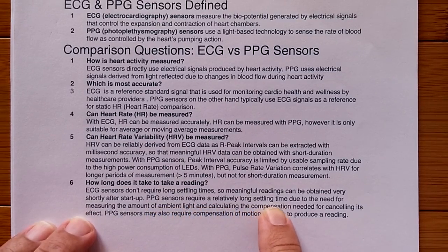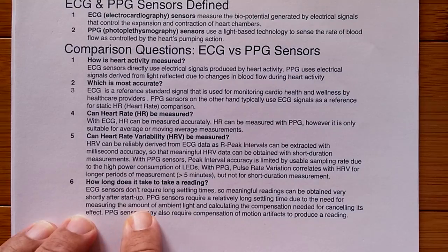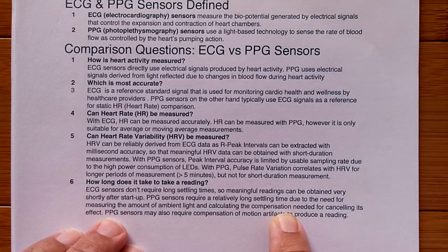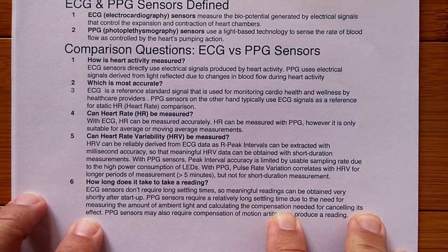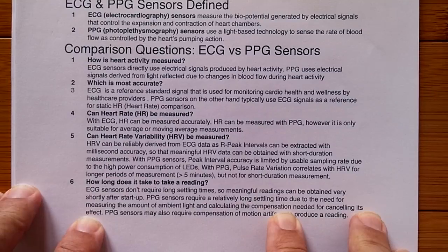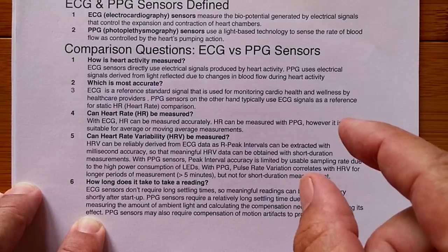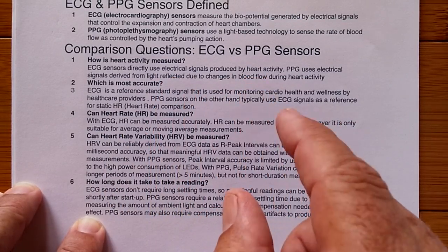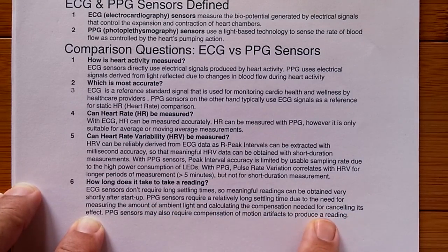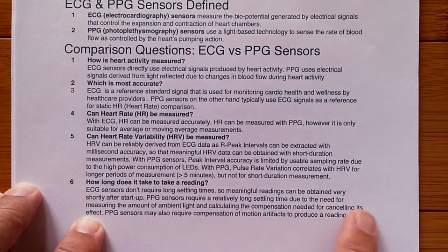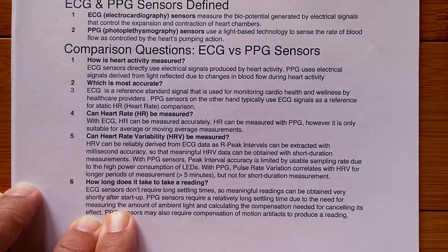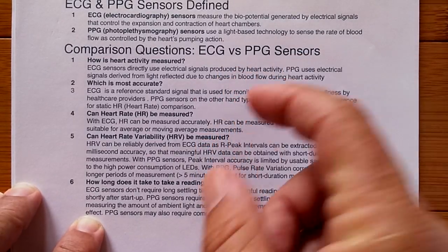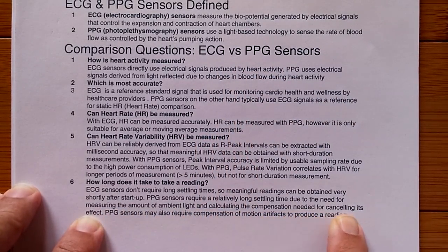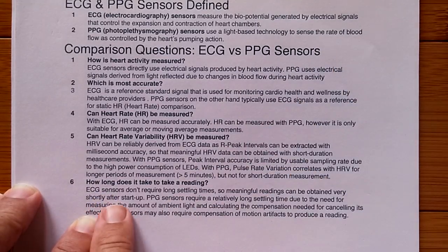PPG sensors require a relatively long settling time due to the need for, you ready? Measuring the amount of ambient light and calculating the compensation needed for canceling its effect. Are you taking your pulse in the dark, in the sunlight? Are you moving? Are you moving in and out of shadow? And all that ambient light has to be added or subtracted correctly to the tiny variation that the light diodes are getting back from the sensors that represents the blood movement through your capillaries. It's really tricky. And they've got big old algorithms to try to cancel out the effects of ambient light. But nonetheless, it can't really start giving you a good measurement, which is why you don't see it right away on your watch, until it's measured the ambient light and compensated for it. Whereas the ECG, boom, it's right there.